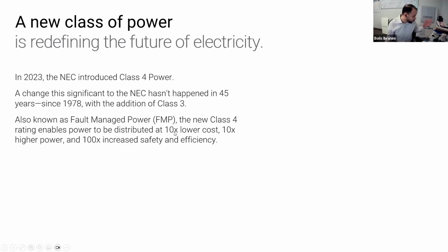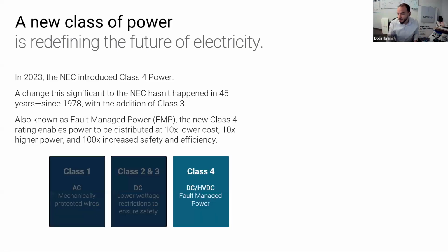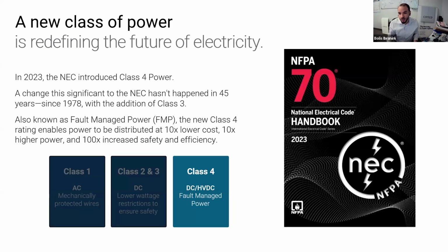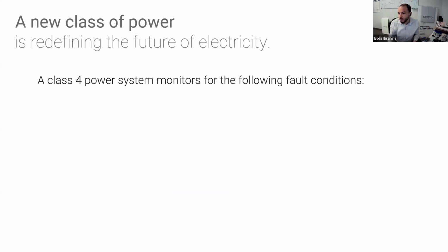It's basically you use low voltage wiring practices. Like here's a fault managed power cable, right? It's twisted pair cable, but you can do 400 volts, and there's no limit on power as long as you respect the ampacity of the cable. And it's making its way to the Canadian Electrical Code. It'll be in the next code cycle. We'll have class 4 in the code book. So that's exciting for us in Canada.